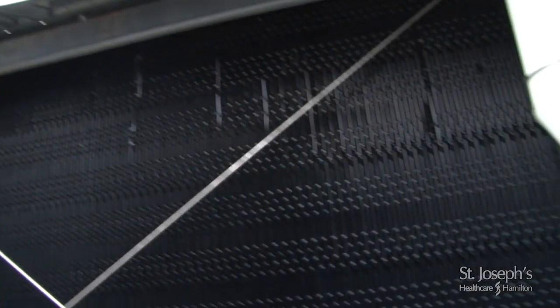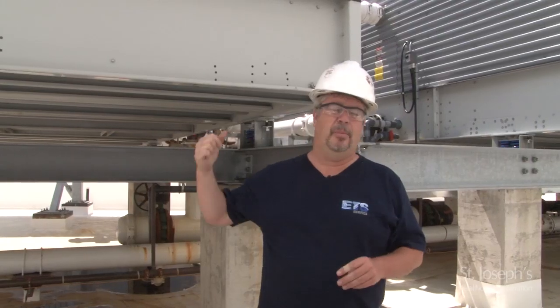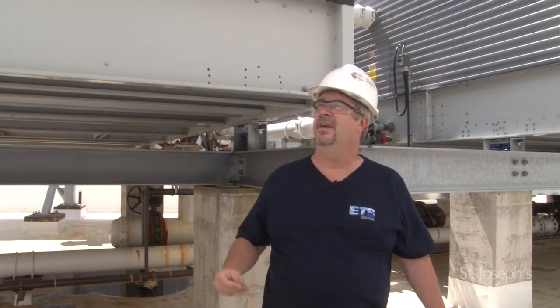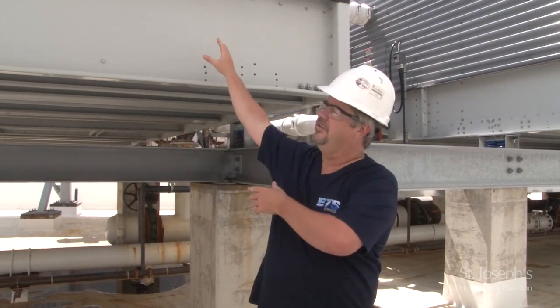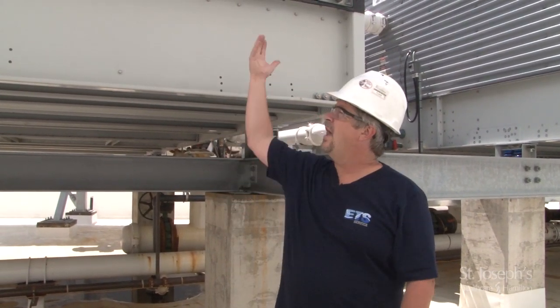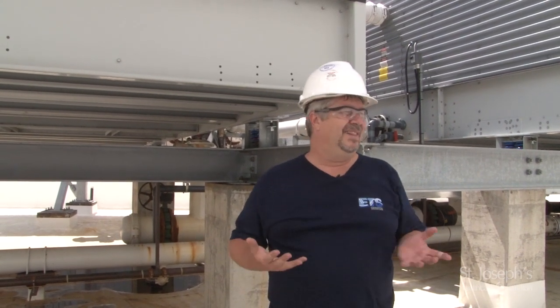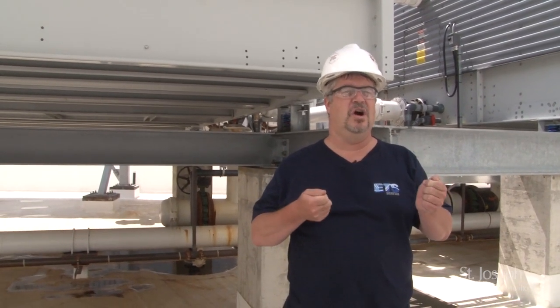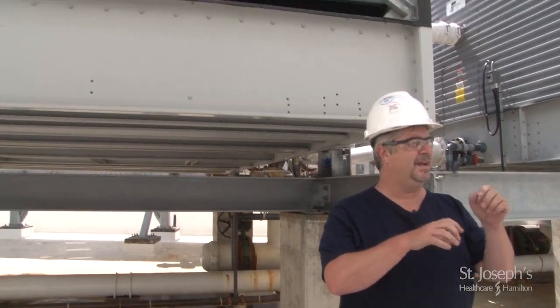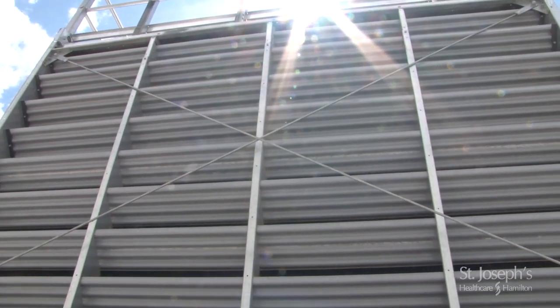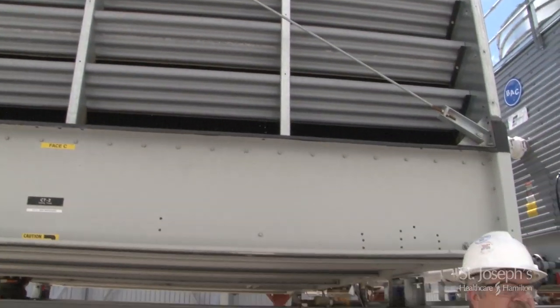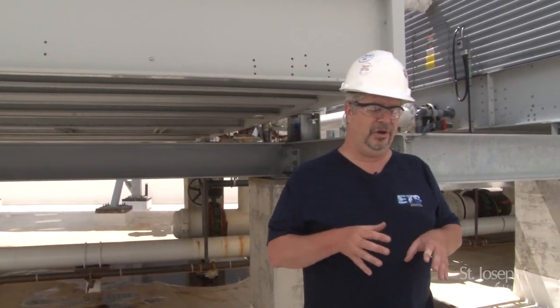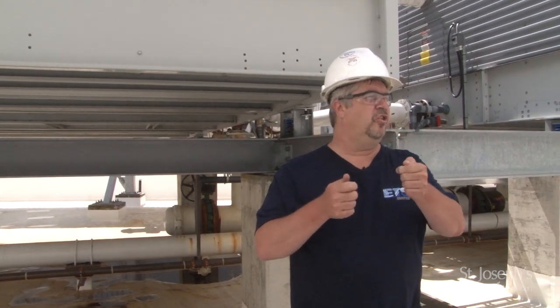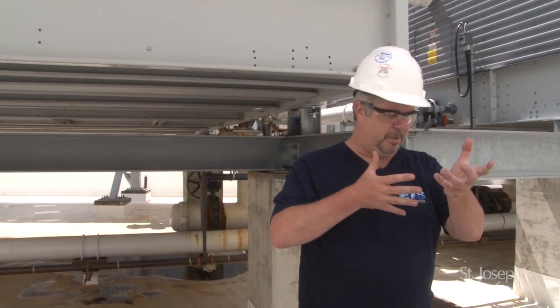The fill pack media will, over time, get fouled up, dirt and debris from inside the piping, dust from the air gets drawn in. All of that, with proper chemical treatment, will clean itself. What we do warn people, it's very tempting, is to grab a pressure washer and try and clean the fill pack because you see a calcium buildup or something like that. That is not good, especially once the fill pack gets a little bit older, gets a little bit brittle. The PSI of a pressure washer will actually start blowing that fill pack apart.